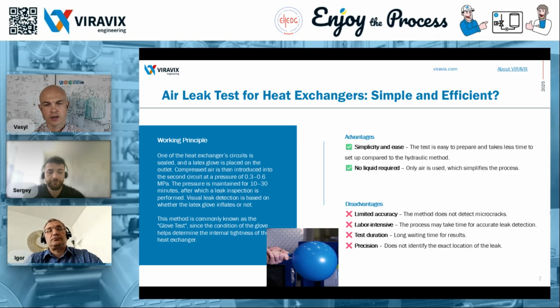Thank you very much. And about the air test, Sergey, I've got a practical question for you. As far as I understand, the traditional way to perform this test is by putting a glove on the outlet of one of the sections we're checking, right? As far as I understand, the glove is held for some time, and then you watch to see whether it inflates or not, because if the leak is small, it probably won't show up right away. Can you tell us, does the temperature of the heat exchanger, like whether it's cooled or not, and the air humidity, do these factors influence the result? I mean, when doing an air test, can you really expect accurate results, or do the testing conditions matter a lot?